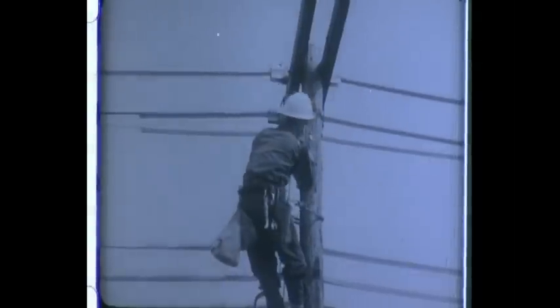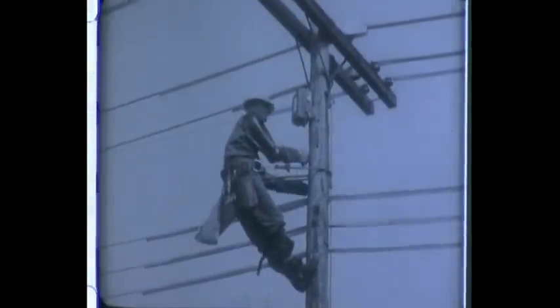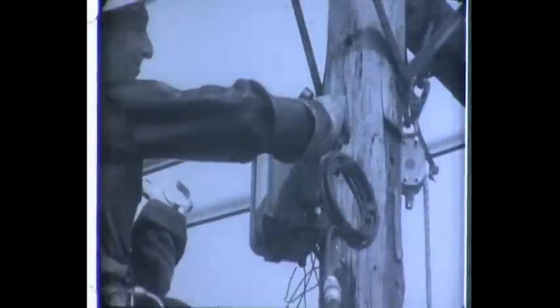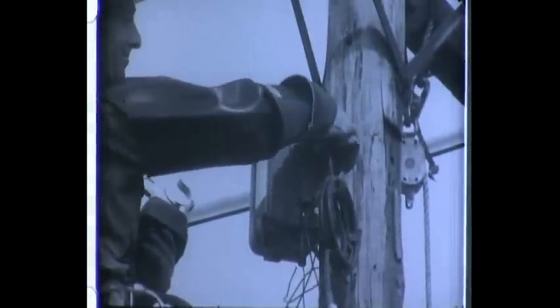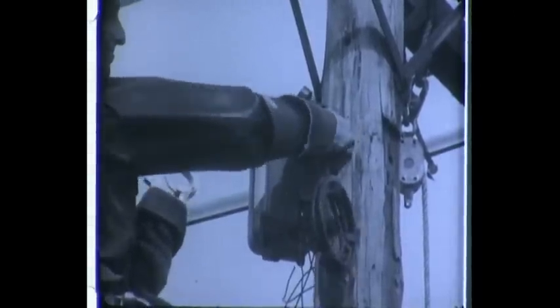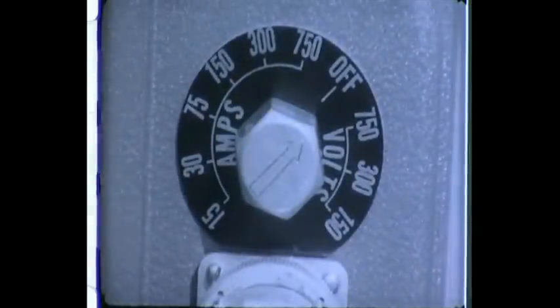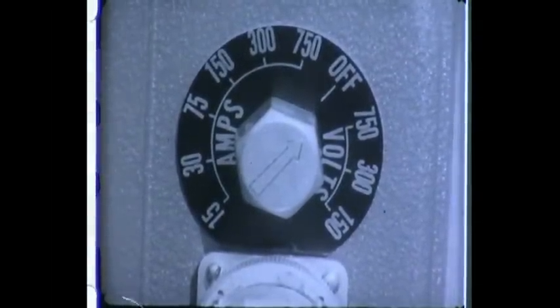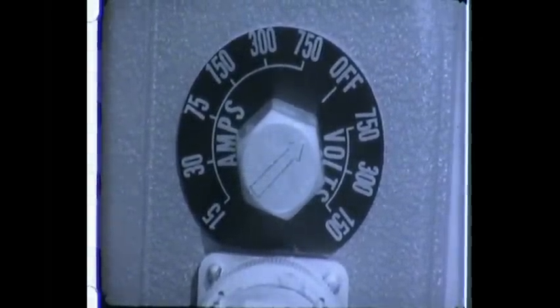First, the CF7 is mounted on a pole or other convenient location with the recorder connected to either a 120 or 240 volt power supply, and then the case is grounded. Then the transformer lead is fastened to the special connector on the side of the recorder. There are 6 current ranges of 15, 30, 75, 150, 300, and 750 amperes.